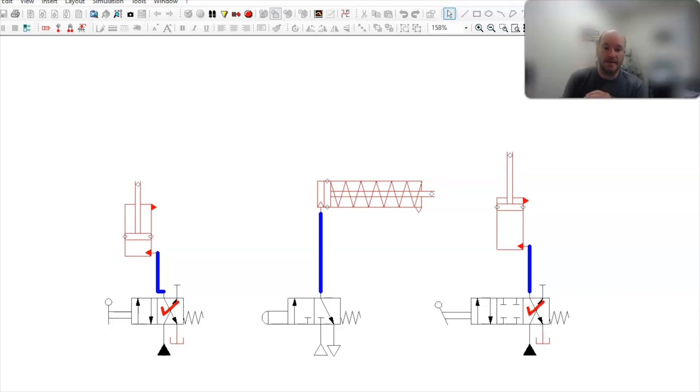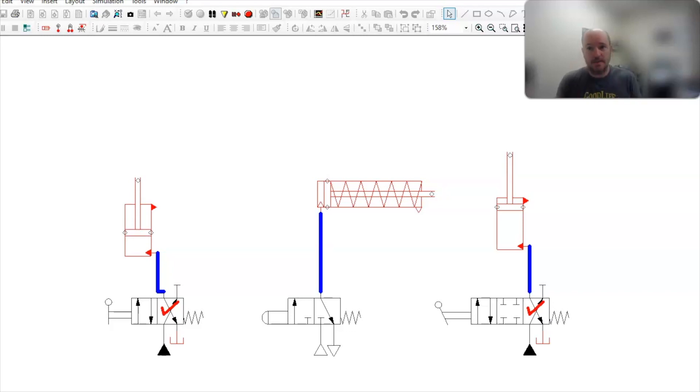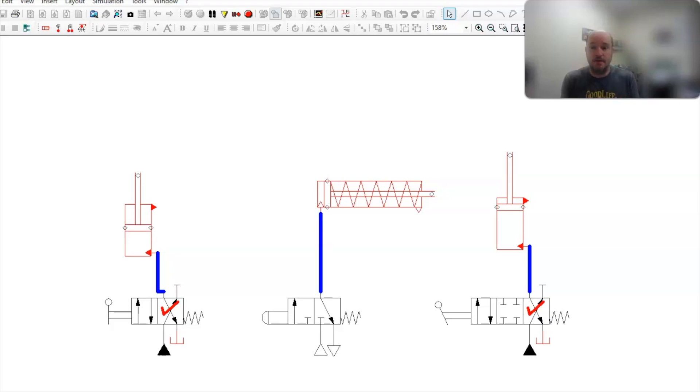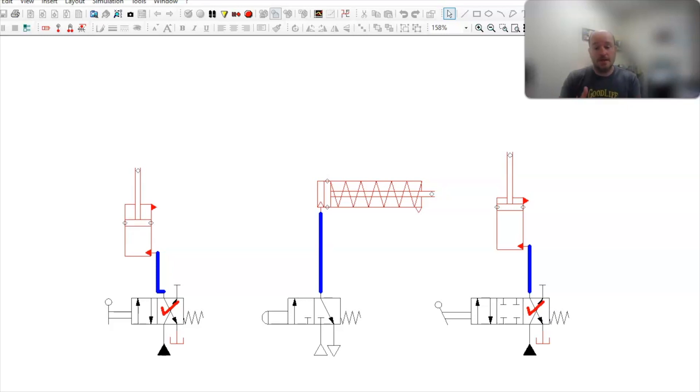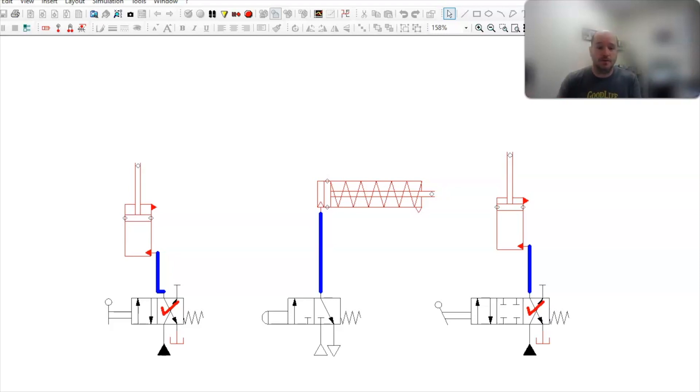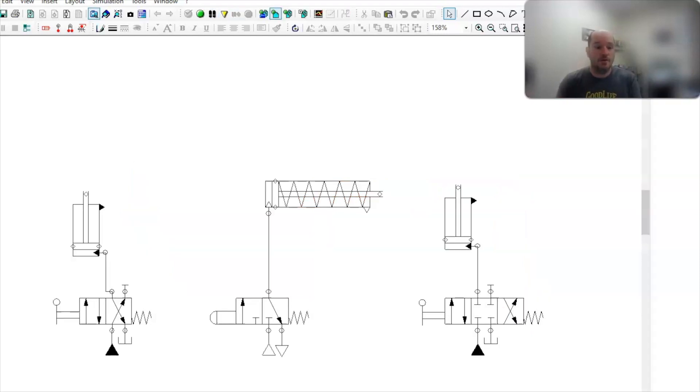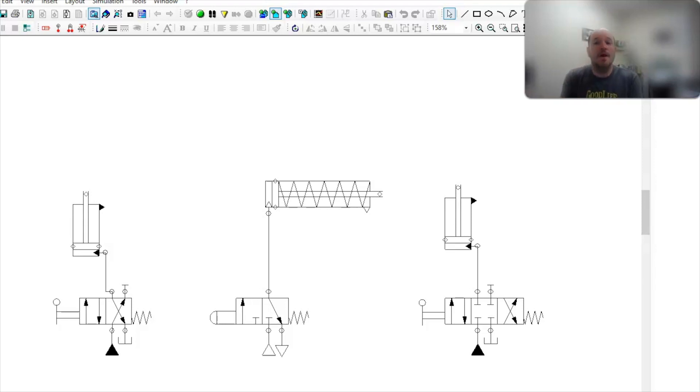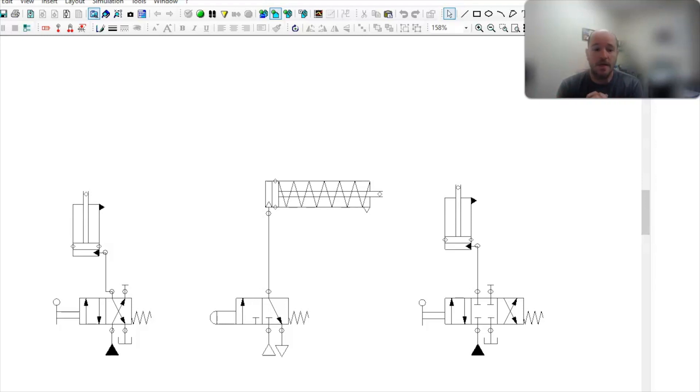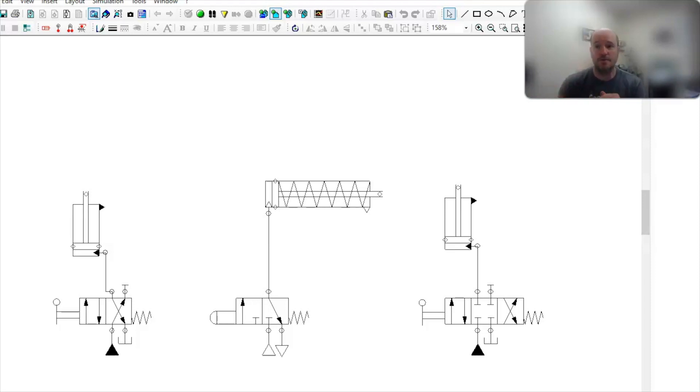So, that's just a little bit of the difference between thinking about controlling a single acting actuator. In my experience, single acting actuators are more common in pneumatics, but they do exist in hydraulics. So, it's good for any technician, hydraulic or pneumatic technician, to understand both of them and how they relate. And, it can be a little confusing because if somebody says, hey, that single acting cylinder, that hydraulic single acting cylinder, is being controlled by a 3-2 directional control valve, and you go, and you look at this, and you say, that's a 4-2. What the heck's going on? Or, if you see a valve with one of the plugs port, typically the B port, but it can be the A port, depending on the makeup of the directional control valve. So, you know, I hope this maybe cleared up a couple questions that you might have about these. Again, if you are interested in learning a little bit more about directional control valves, I do have other videos on that that, again, will be linked at the end of this video. So, anyway, thanks for watching, and I hope you enjoyed the video.